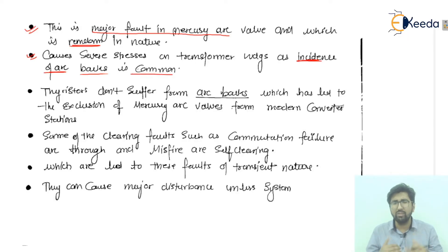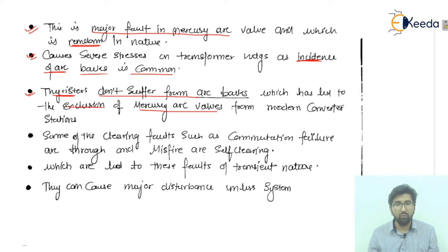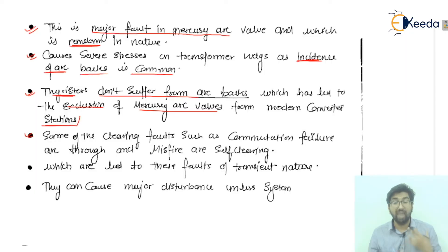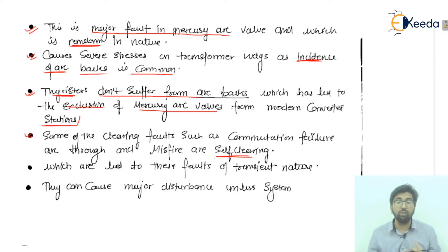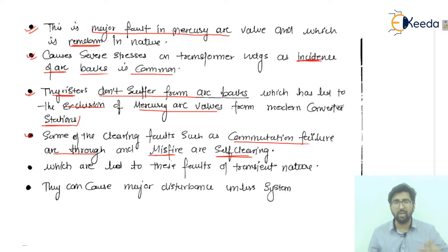Thyristors do not suffer from arc backs, and this has led to the exclusion of mercury arc valves from modern converter stations. Some faults such as commutation failure, arc through, and misfire are actually self-clearing faults. If a question is asked about which fault conditions are self-clearing: the first is commutation failure, the second is arc through, and the third is misfire.